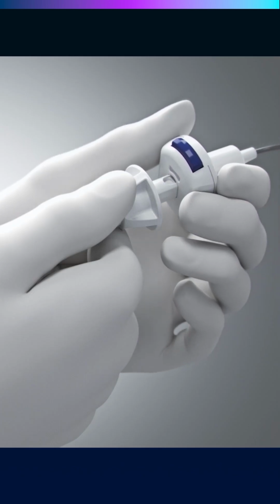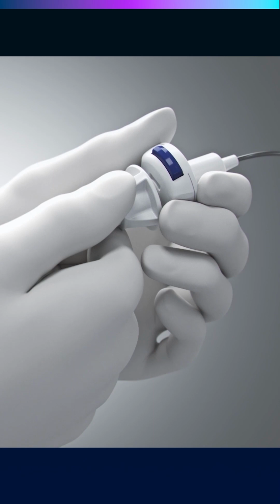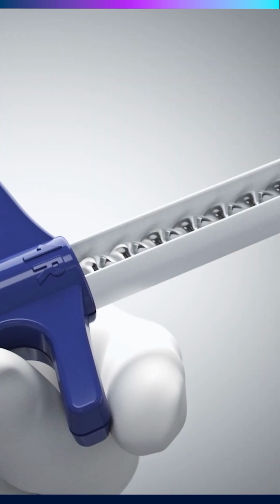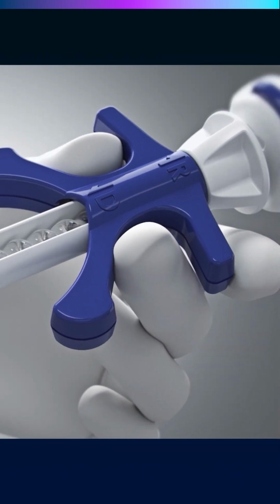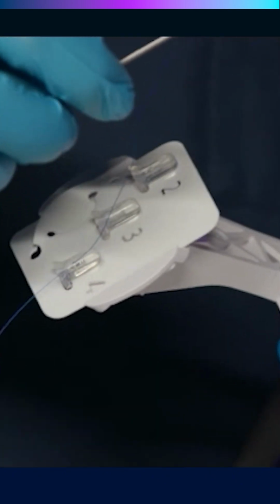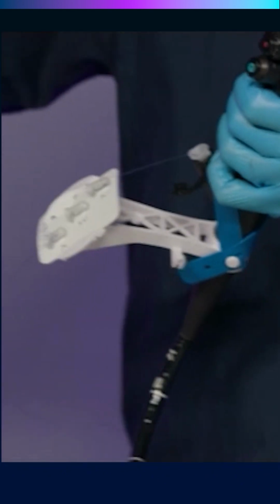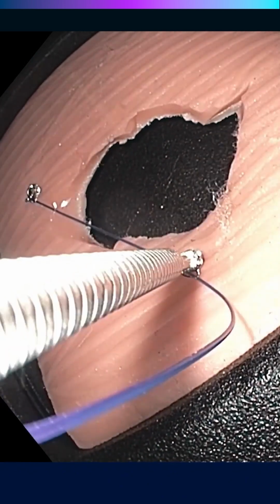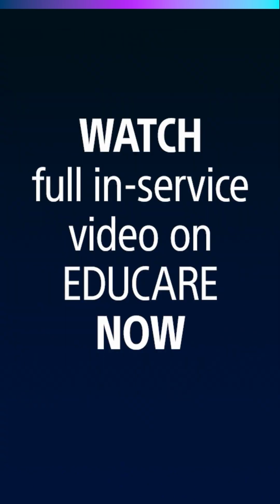Reset the handle by sliding the push catheter back to the lock position until it clicks into place. Move the handle slider to the R position. Reload the second Helix Tack by securing the distal end of the catheter, maneuver the scope, and target the second position. Repeat technique for each additional Helix Tack.